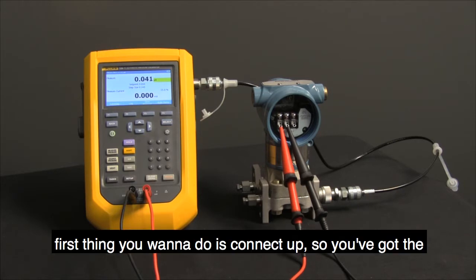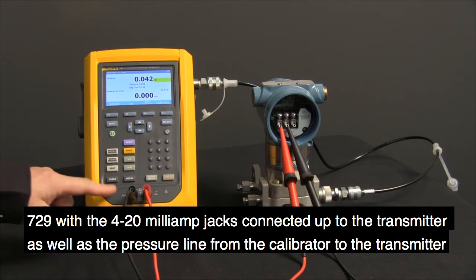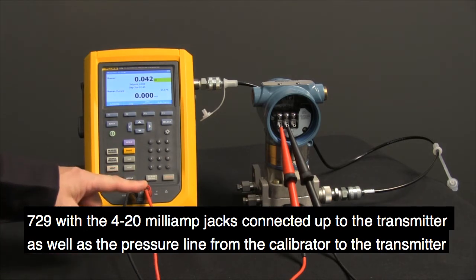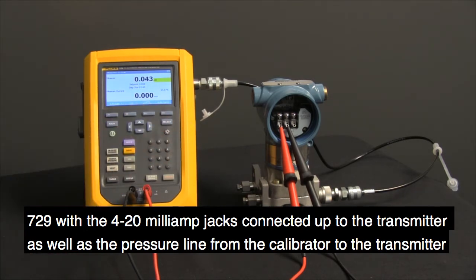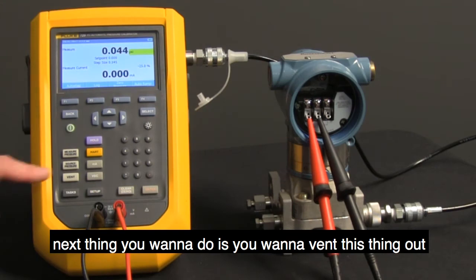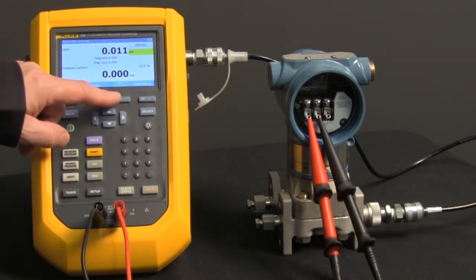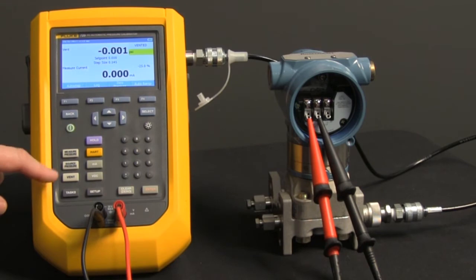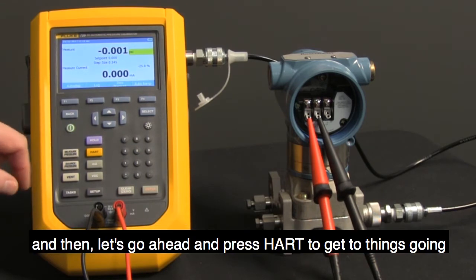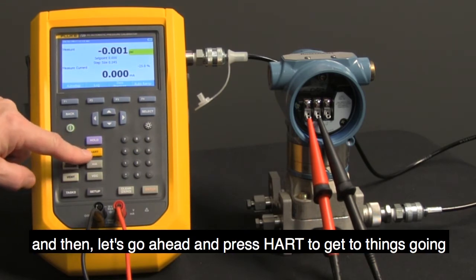First thing you want to do is connect up. So you've got the 729 with the 4-20 milliamp jacks connected up to the transmitter, as well as the pressure line from the calibrator to the transmitter. Next thing you want to do is vent this thing out, zero your pressure, and then let's go ahead and press HART to get things going.